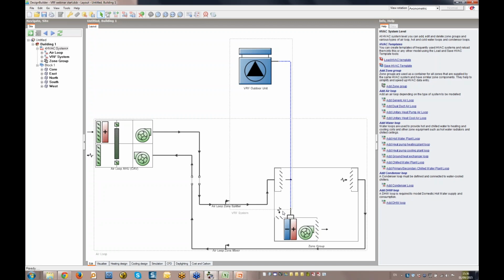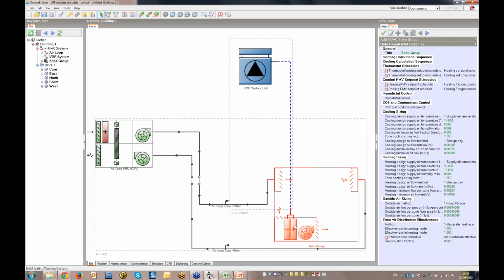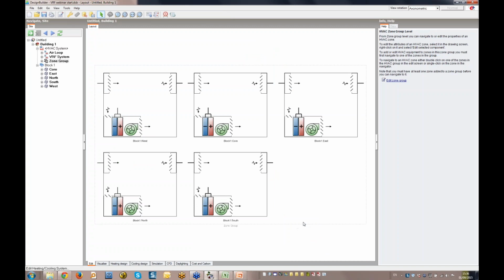Before looking at the component parts of the system, I'll explain DesignBuilder's zone group concept. In this case, the schematic diagram shows a single zone group served by the HVAC plant. All zones served by the same HVAC system are grouped together. If I navigate to the zone group, you'll see all zones represented. Using zone groups in this way simplifies the schematic, which would otherwise get very complex for a building with many zones and HVAC systems.